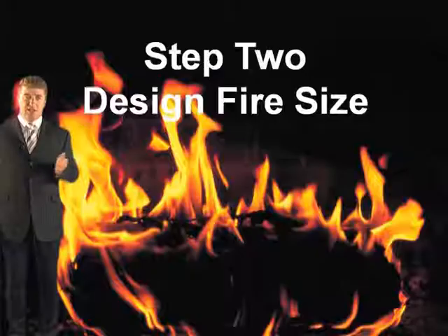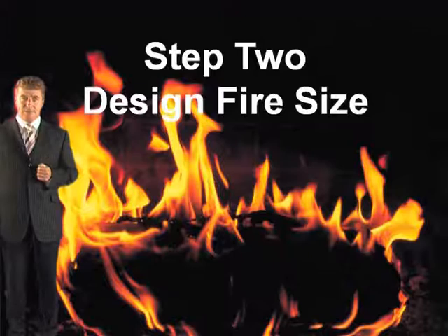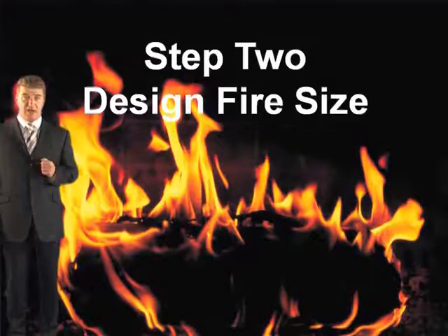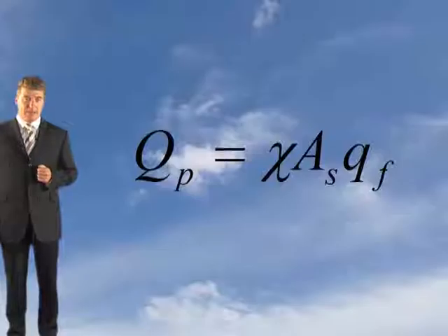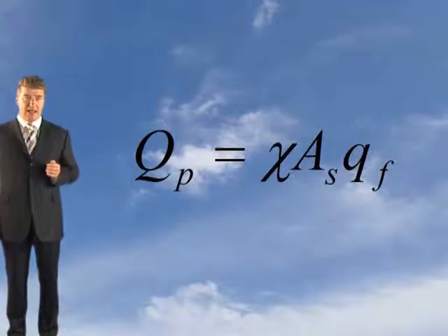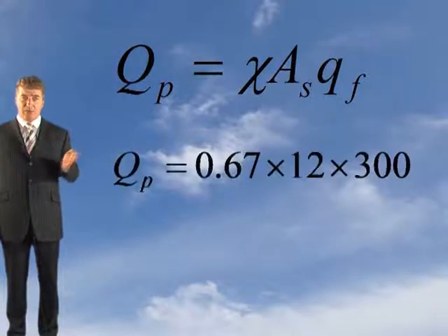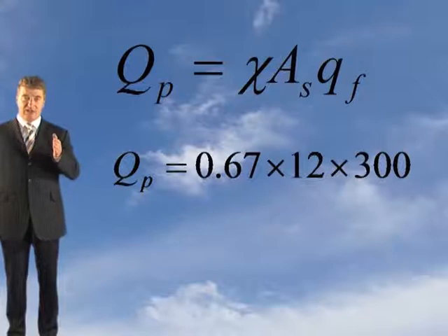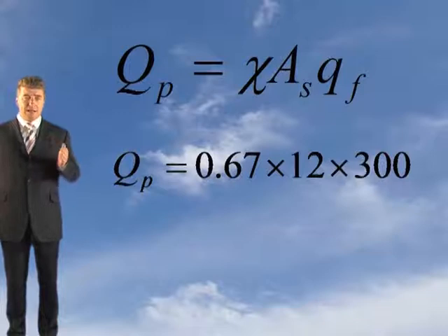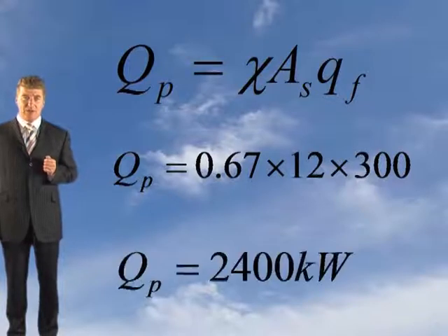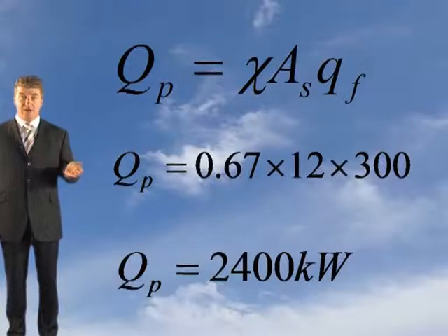Step two is to determine the design fire size. The formula to determine the fire size based on the information provided is: QP equals chi times AS times a QF. In this case, Chi equals 0.67, which is the default value for most things giving off that same convective heat output. Times 3 by 4 is 12 times 300, which gives you a design fire size of 2,400 kilowatts or 2.4 megawatts. That covers step two.